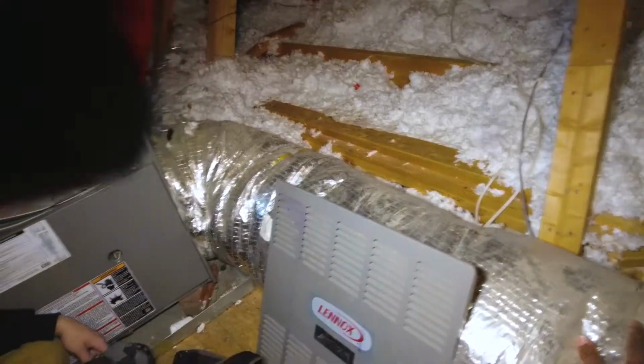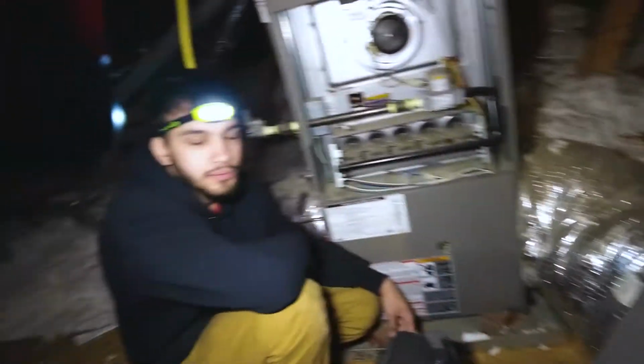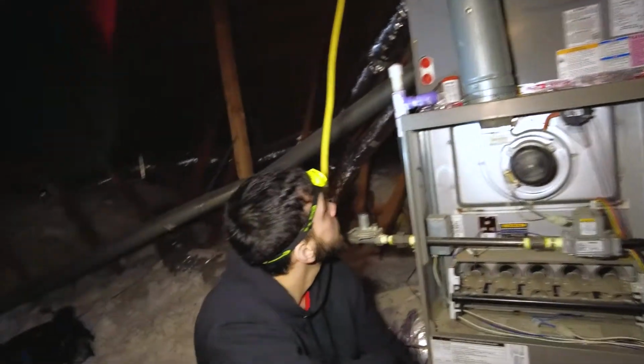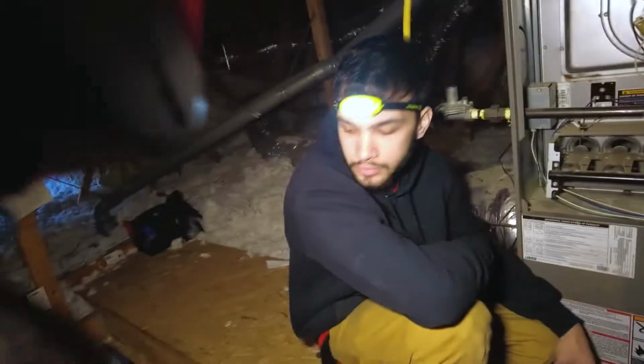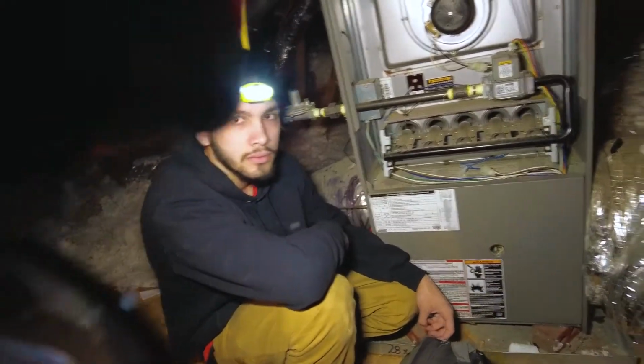That's something we definitely want to document if it is undersized. But a lot of times you might find a collapse, someone might have stored something on top of these, and you'll see it flattened in a spot, or you might have too many dampers off. Another thing, sometimes the homeowner will close a lot of the registers off in the house, closing those vents where we put the psychrometer in.